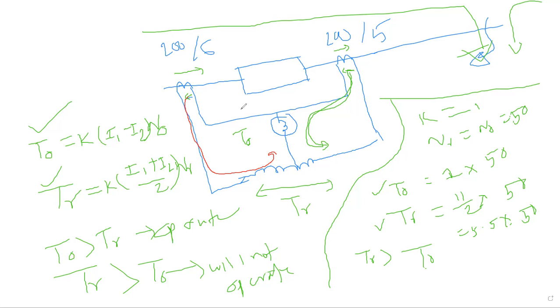In the case of only a differential relay, we have already discussed that under this consideration the differential relay would have operated. But that was the limitation of the differential relay, which has been resolved here. You see, in the external fault consideration the two CTs are not identical, but still this differential relay is not operating. So that means it is a better version of the only differential protection relay. Understood? Understood or not? Yes, sir. And obviously, if the fault is internal, the relay will operate.